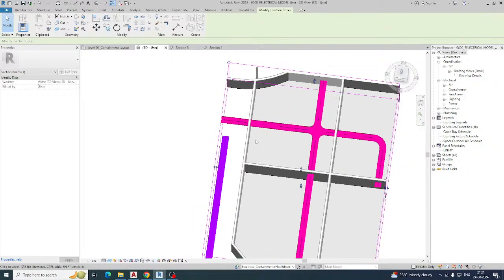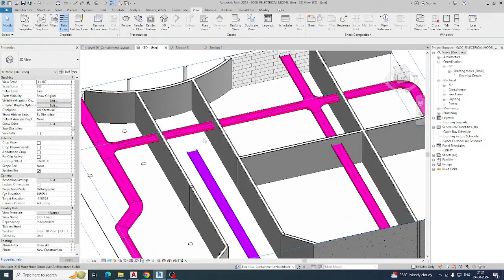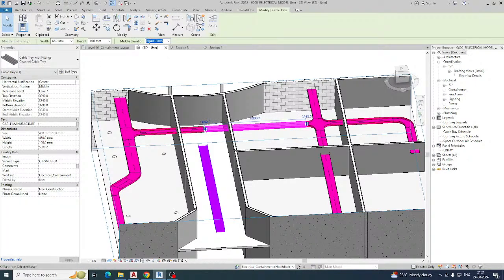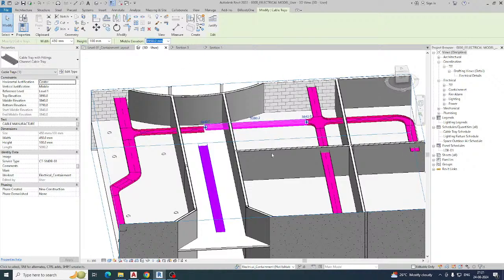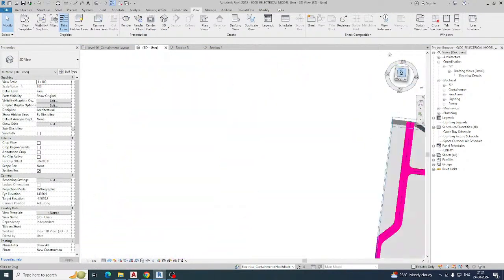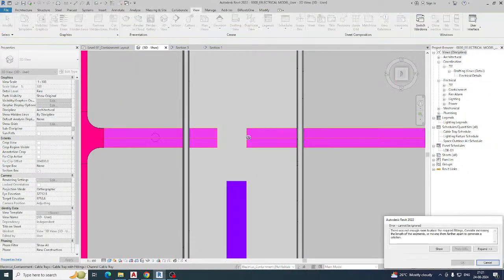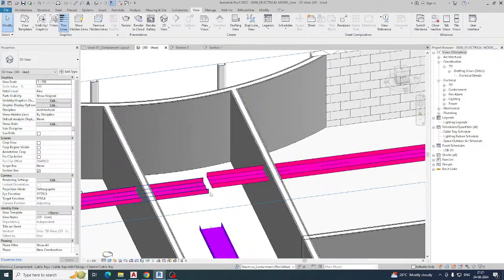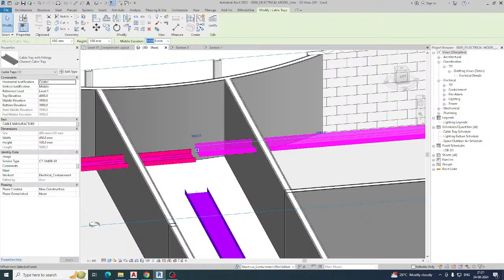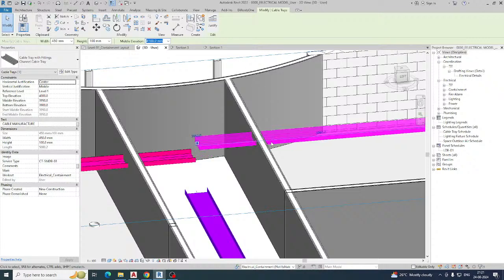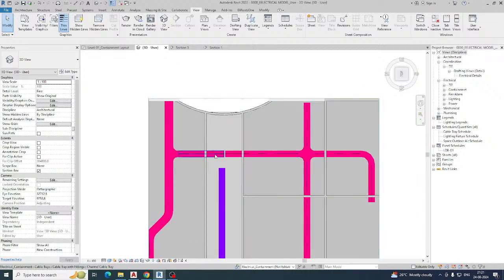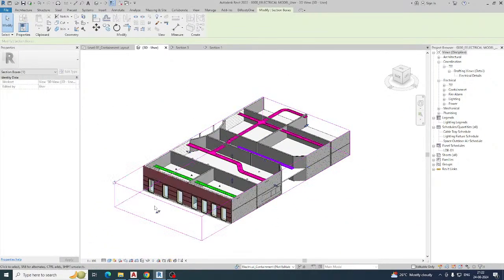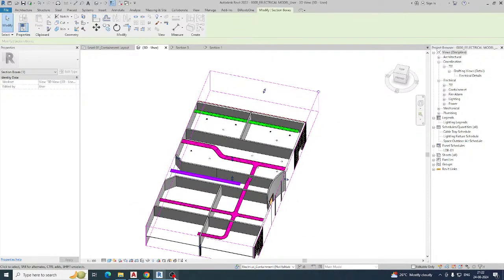If you need to split a cable tray — for example, a duct is coming through and you need to raise the cable tray — use the Split command (SL). Set a new height, for example 4100, for all cable trays in that zone. Then go to the top view, select and connect the elements — they will connect automatically. This completes the exercise. If you found this video helpful, please subscribe to my channel. Thanks for watching.